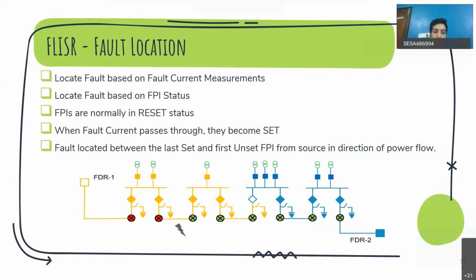So if you are taking fault current measurements at the substation and at different RMUs, you can locate the fault based on those measured fault current values, or you can locate it based on the fault passage indicator status. I was talking about this fault passage indicator status initially when we saw RMUs. Normally they are in reset condition. Whenever fault current is passing through them, they automatically go into set condition.